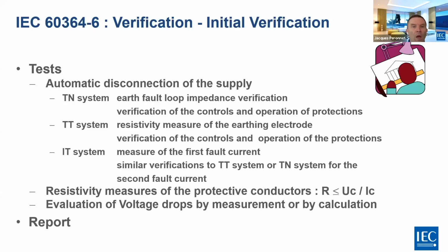And we are also going to make some functional tests. Regarding automatic disconnection of supply, in a TN system you are going to verify the earth loop impedance, and you are going to verify the control and operation of the protection. In TT, you are going to verify the resistance measure of the earthing electrode and the verification of control and operation of the protection. In an IT system, you are going to measure the first fault current to make sure that it is not a hazardous current. And you are going to make verification similar to the TT or TN system for the second fault current.